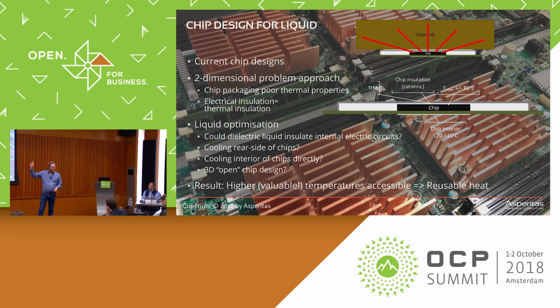But that temperature measurement is actually taken on the exterior of the chip. Between that measurement point and the interior of the chip is still a layer of ceramic or another material, which is at least electrically insulating. But that also means thermally insulating. So there's always a boundary layer on top of a chip that acts as a thermal barrier.